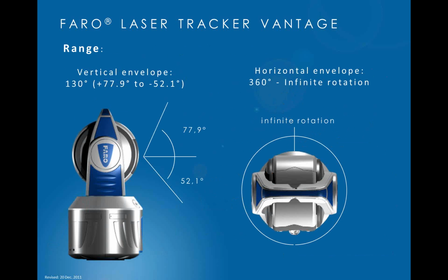The vertical envelope for the tracker is 130 degrees, an improvement on the previous laser tracker. It also has infinite rotation in its vertical axis as well as horizontal, so there are no end stops where you might track to an end stop and it binds up, requiring you to walk around the opposite direction to get where you want to measure. This makes it very easy for the operator to measure wherever he puts the laser tracker.